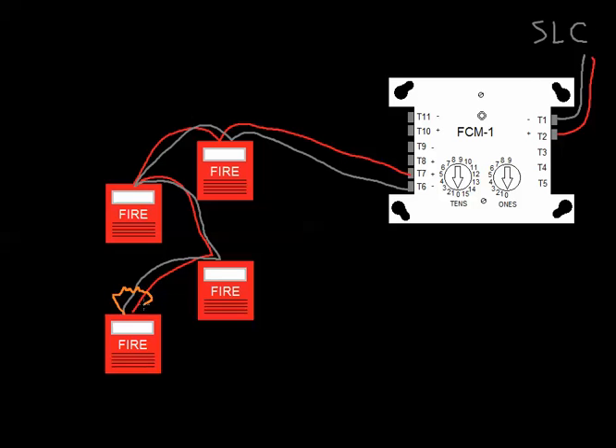So this is a pretty bad drawing. I apologize. But we're going in and out of each one of these horn strobes. And in this case, the supervisory voltage or the supervisory current that's flowing through this circuit and through the end line resistor is taken from the data, right from the SLC. So it's a very low voltage, very little amount of current flowing.